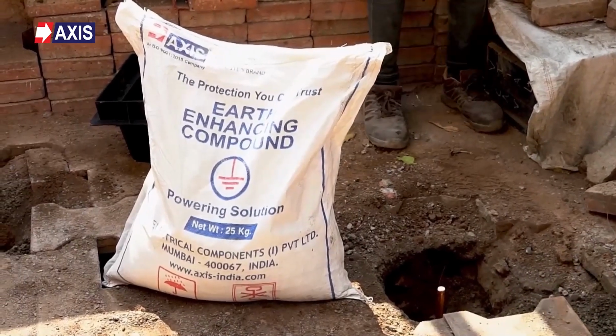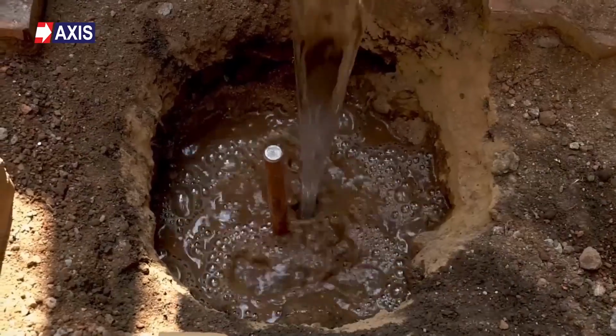So, what is this backfill that we keep talking about? Backfill, also known as earth enhancing compound, is a material used to fill the area around an earth electrode in an earthing system. It's an important part of the earthing system because it has a hygroscopic property.